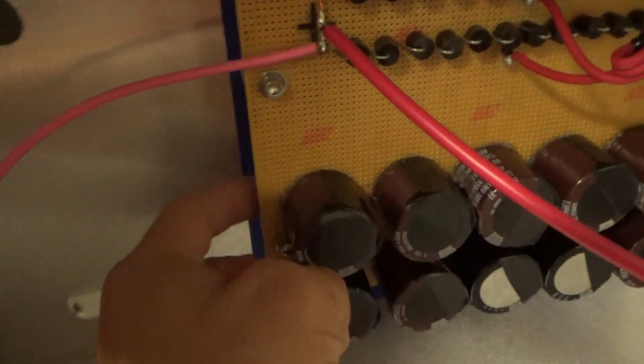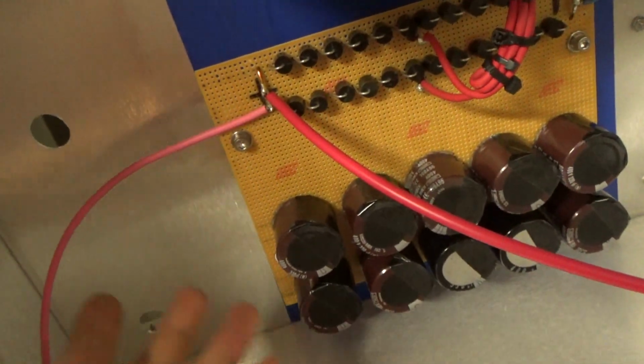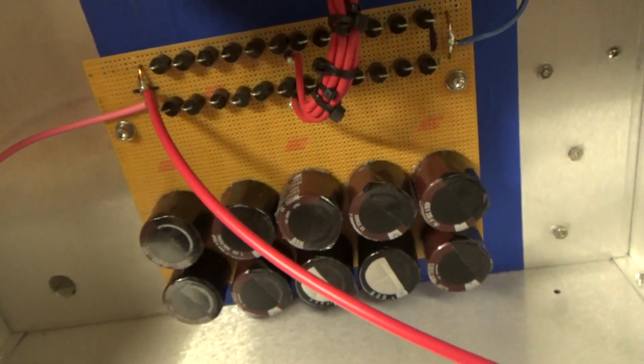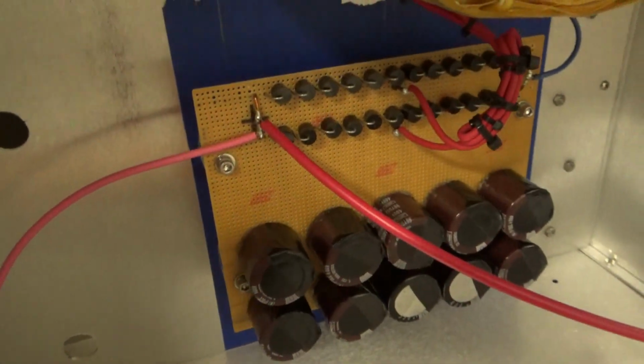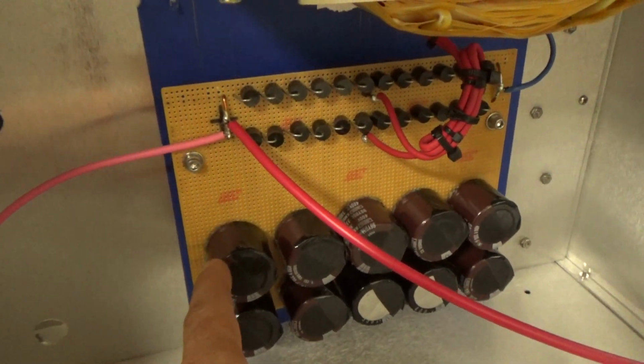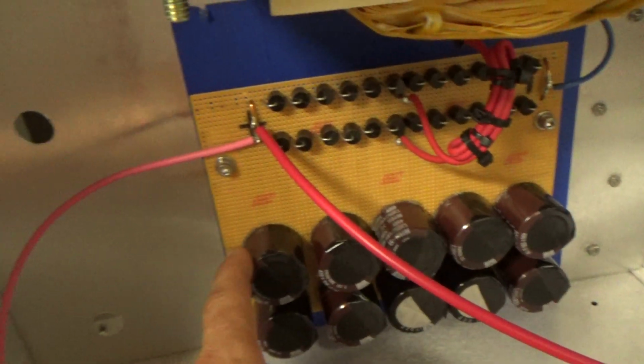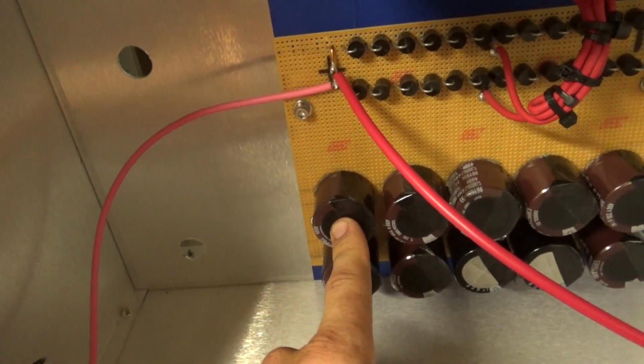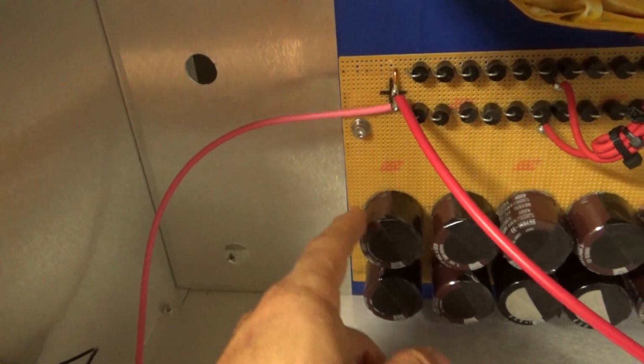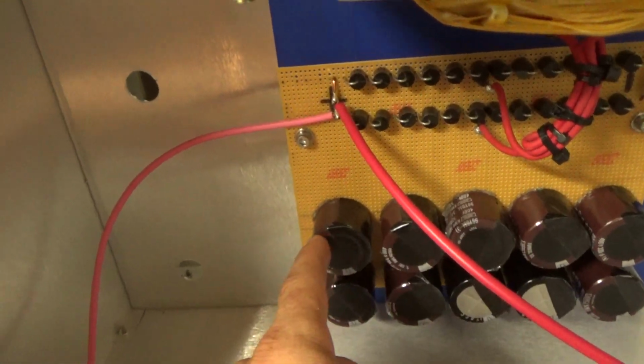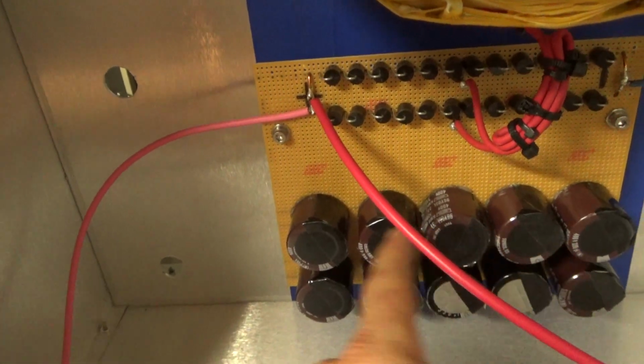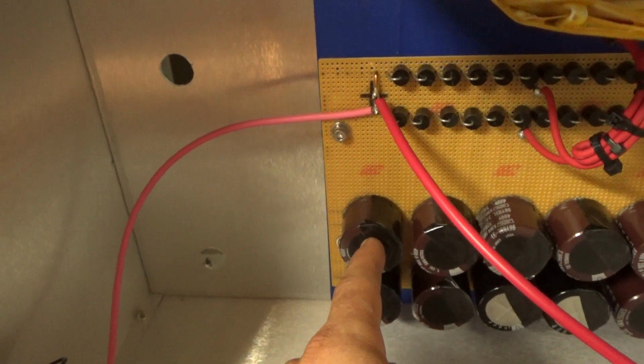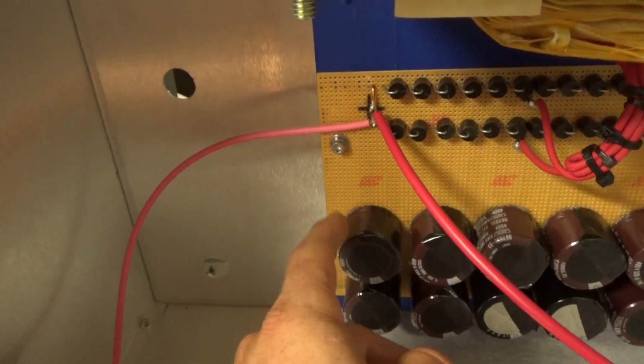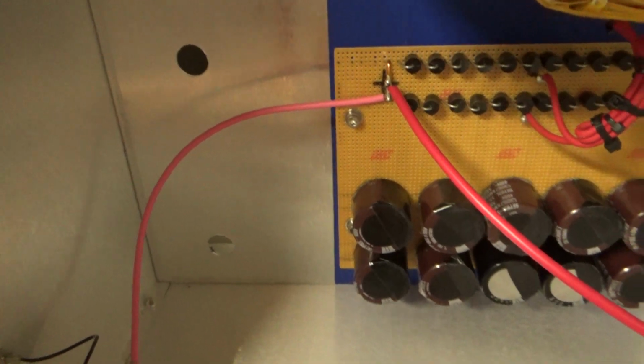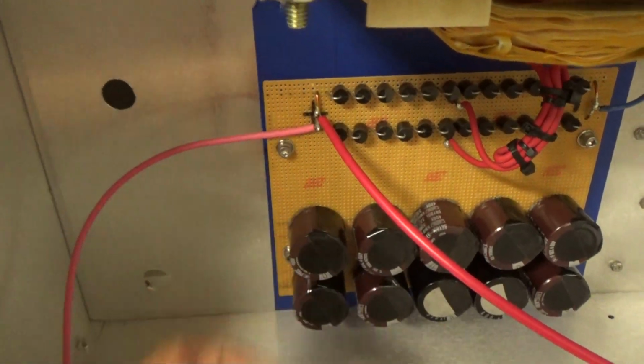The bleeder resistors are across each cap. I've not taken this board out. Who knows what they are. I don't have time right now to pull the board out, so I'll find out later on. But you should always have a resistor across each cap when you're using caps in series. If a capacitor isn't rated for the total voltage that you have on the power supply, you always want to have a resistor across each cap to equalize the voltage, so one cap doesn't have an unequal amount. If that happens, you could damage the cap and then it'll fail. You'll pierce the insulation within the cap.